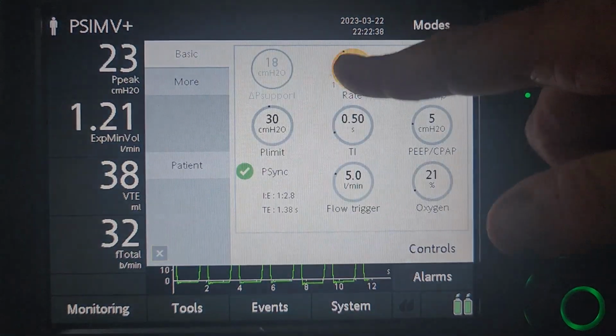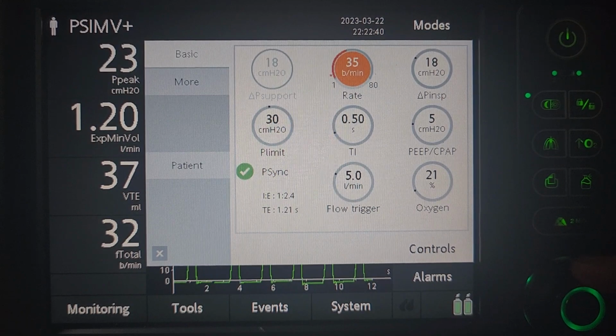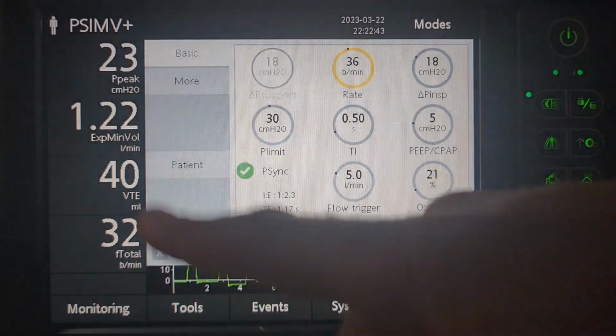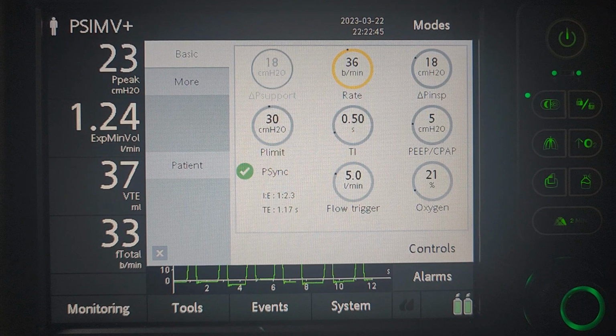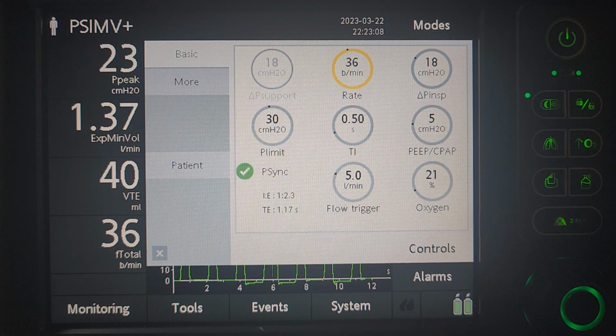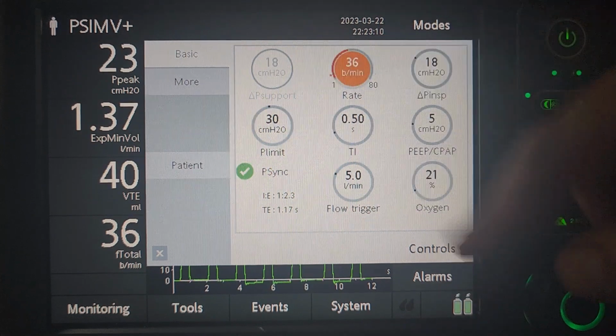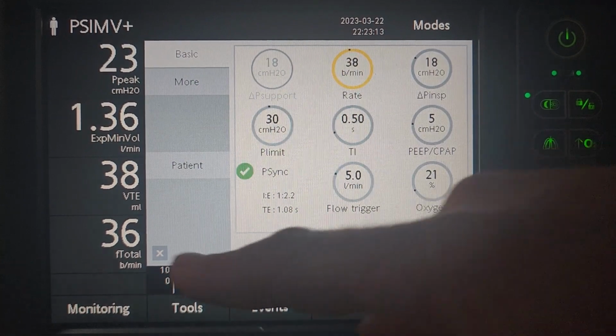We can go back into our controls and we can increase the rate. Let's try 36. Let's look at our expiratory minute volume and see what it does. And we should see an immediate feedback in pressure mode. So we're increasing. We could go up to 300 per kilo for an expiratory minute volume. So that'd be 1.5 liters per minute. So let's increase that some more.